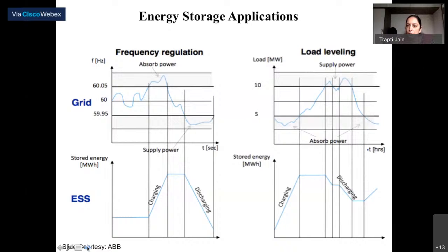The next application is load leveling. We usually want the load curve to be level, as flat as possible, although exact flat cannot be obtained. Here we want it maintained between 5 to 10 megawatts. Initially the load was less than 5 megawatts, so we started charging our energy storage systems. So load can increase at that time and it is maintained within the desired band, then it is constant.